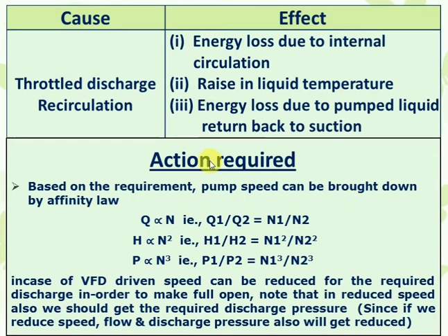In this process of reducing speed, we should keep in mind that head is also directly proportional to the square of speed. So if we reduce the speed, discharge flow will come down and discharge head and discharge pressure will also come down. We should not let the discharge pressure go below the requirement — for example, if the pump is operating at 5 bar and the requirement is 4 bar, reducing speed should not bring it below 4 bar. We can then calculate the power difference, and the difference between both powers is our gain, which can be easily calculated using the affinity law formula.